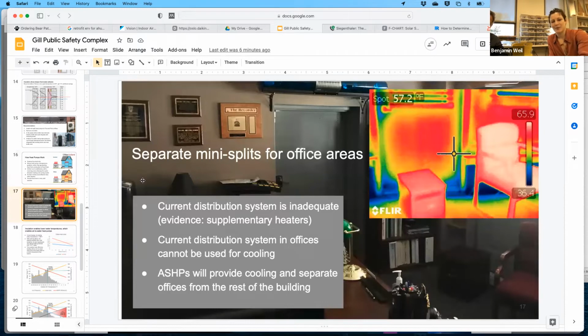So why separate mini splits for office areas? Our main reasoning is that the current distribution in the office areas is inadequate. Our evidence of this was when we went there, they had some space heaters around. And here's actually an infrared photo that we took in one of the offices. I don't know if this looks familiar to anyone. And you can see how cold that wall is, right? That wall, where it's the concrete portion of the wall, is really cold. And that is making it so that the distribution system that exists is insufficient to satisfy the heating demand.